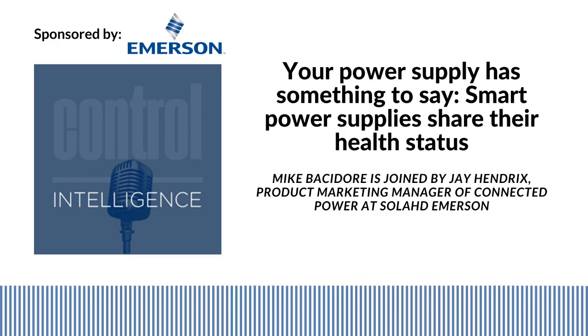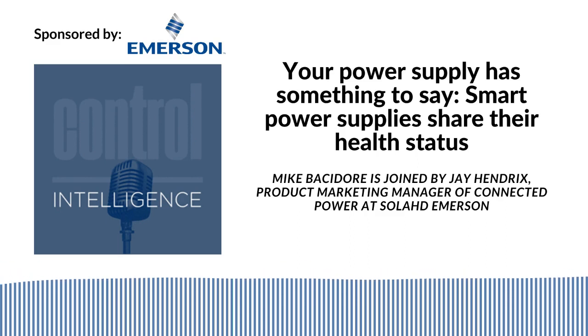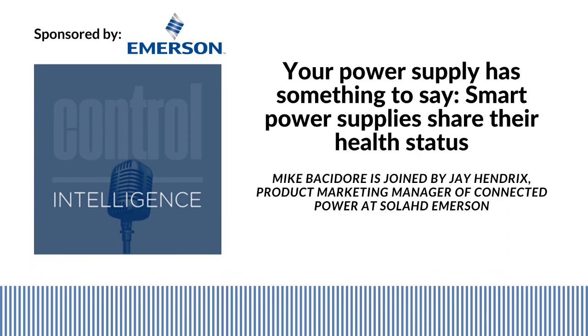manufacturers are providing ways of knowing or giving you a better indication of what is the life left in a power supply. And that could be done by providing you the runtime hours. And you can monitor the runtime hours from inside the power supply and compare that to the specification data. So hey, I've been running at 50,000 hours or 100,000 hours. Well, my power supply is rated at 200,000 hours at a certain temperature. This means I have so many hours left. So I've got to start thinking about replacing this power supply.